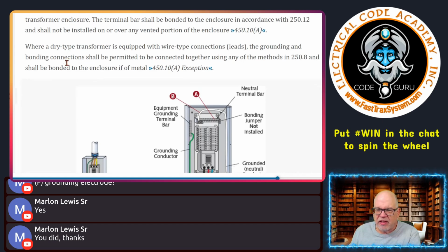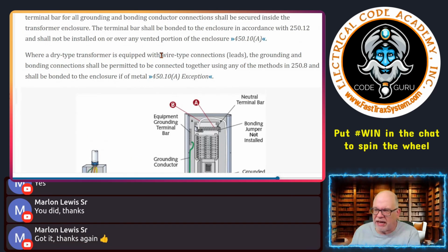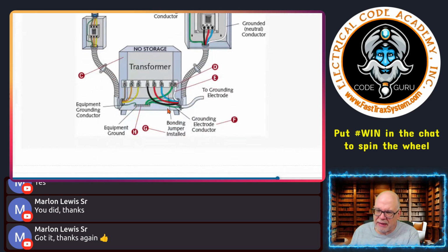Okay, now it says where a dry type transformer is equipped with a wire type connection, leads, the grounding and bonding connections shall be permitted to be connected together using any of the methods in 250.8 and shall be bonded to the enclosure if of metal. So sometimes you've got leads, or depending on the transformer, termination leads or whatnot. Again, the key takeaway for most people is that in this transformer you're usually going to have lugs. It's going to be a lug bus mounted in the actual transformer. So interesting about a separately derived system, the primary side does not come in contact with the secondary side except through the grounding and bonding. And that's okay. That's fine. It's still considered a separately derived system.